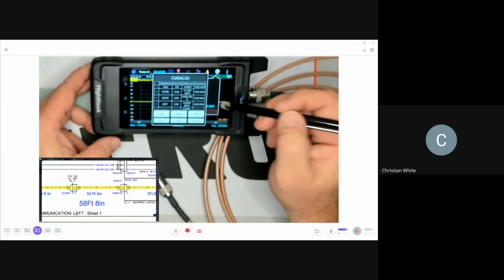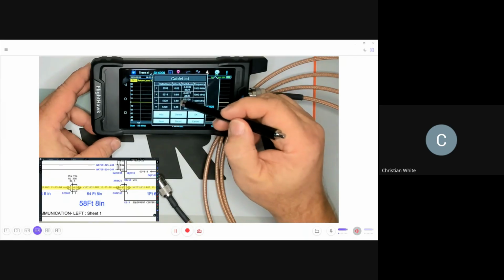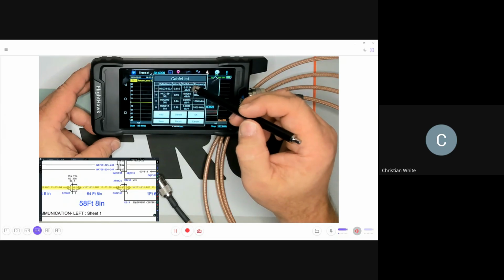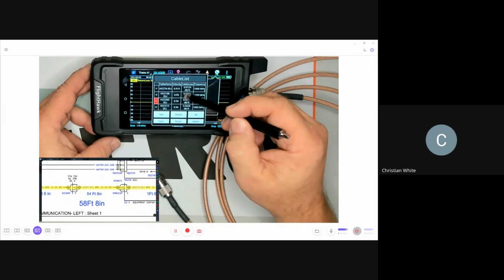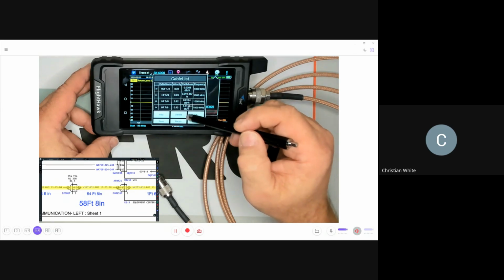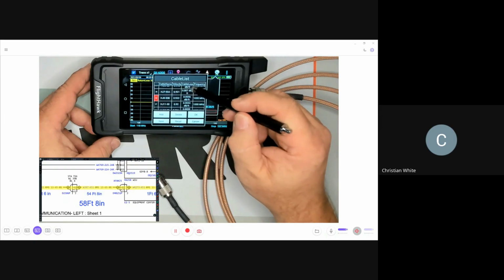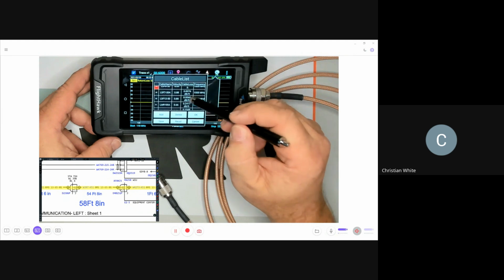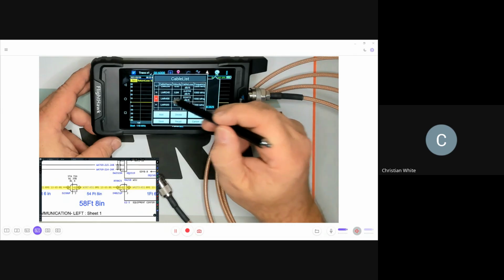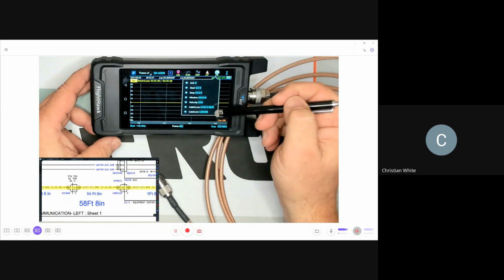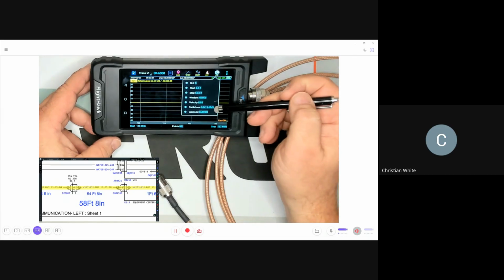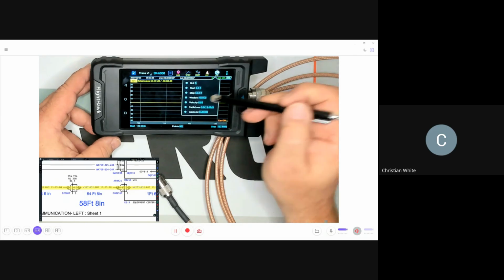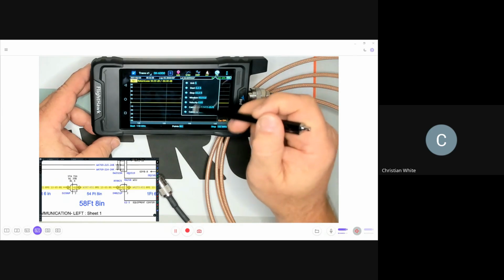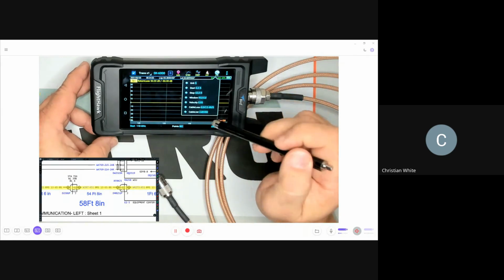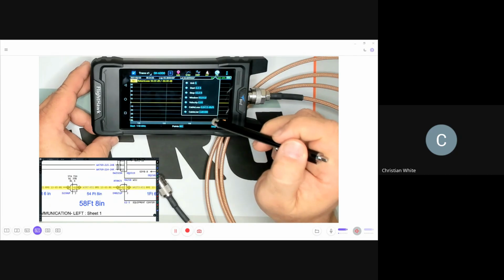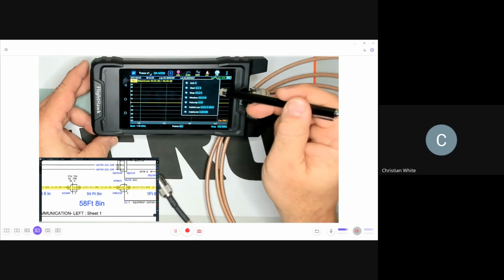There's a cable list built in, so we pick what our cable is off the list and click on it. This Sitehawk has older software on it. I tried all morning to update it to get a better list. You can always add it in manually, but for our purposes today, we're going to click. It doesn't have our specific cable in here, but it's close to the 400. So we click on this, click OK, and it propagates our cable loss per foot and our velocity. If you have questions on that, call me and I can walk you through it. I don't know if Atlas updates their firmware on these regularly. Worst case, we can look up this information and put it in manually - not that big of a deal.